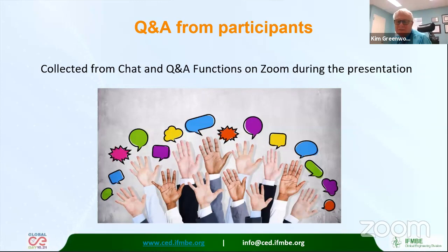That is something that's done typically through our medical device processing group. And they're the professional group that monitors that. We should, as clinical engineers, have a good understanding of sterilization techniques. At least I believe so. Yeah, we understand that all the medical devices come with manuals, and they have all the information from the manufacturer. What are the proper disinfection protocols that need to be done? And normally we train the end users on the proper disinfection. So training on proper handling and disinfection is definitely done by the clinical engineers. We organize the training with the vendors when we buy new systems.